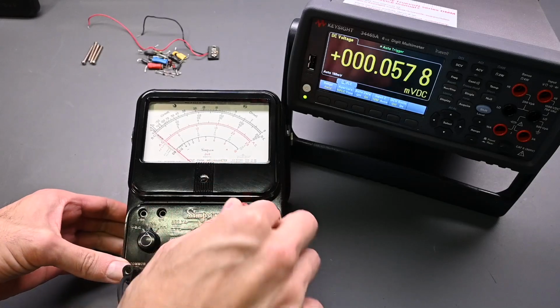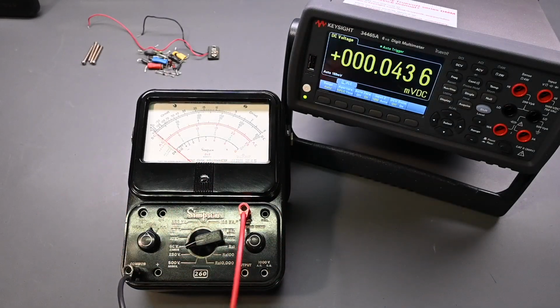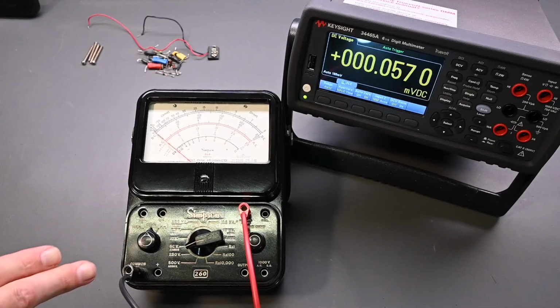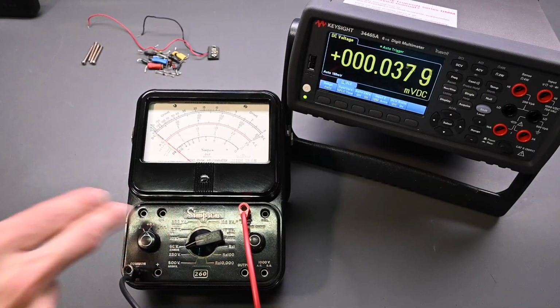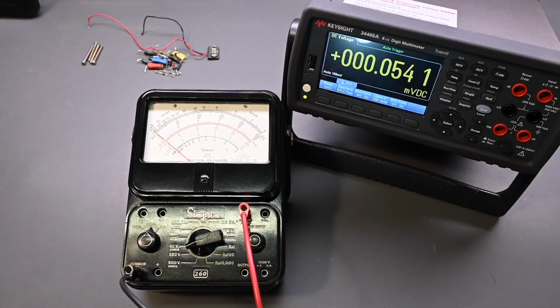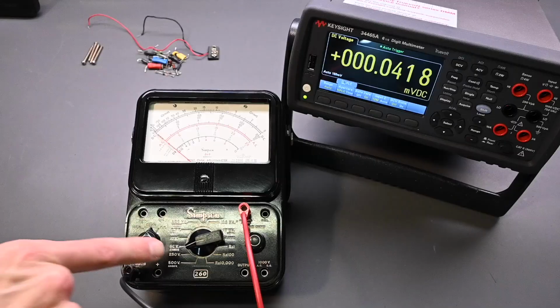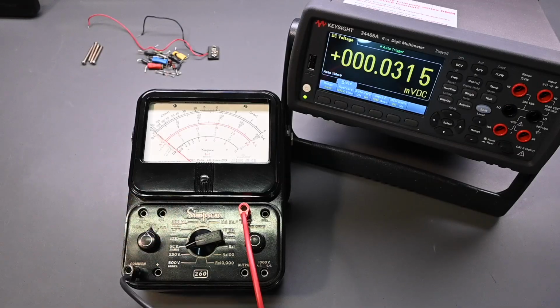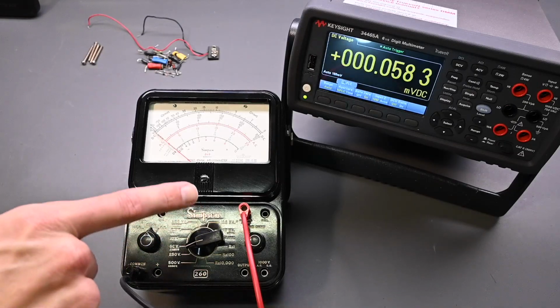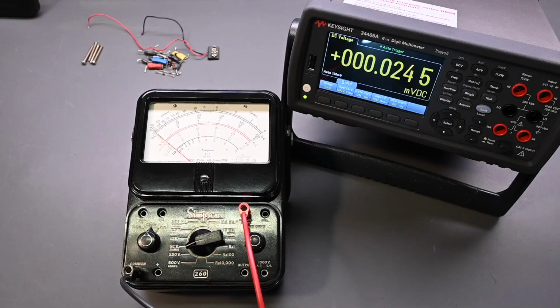on the 250 millivolts. So as you recall in the part 1 video, when I was checking the various resistances as I stepped through the voltage ranges, the numbers were off by quite a bit, and I want to make sure that those numbers look correct now. So this meter has a 20,000 ohms per volt rating. So when you take the full scale voltage reading and you multiply it by 20,000, that's the resistance you should see on the input of the meter. So starting on 250 millivolts, 0.25 volts multiplied by 20,000 should be 5,000.